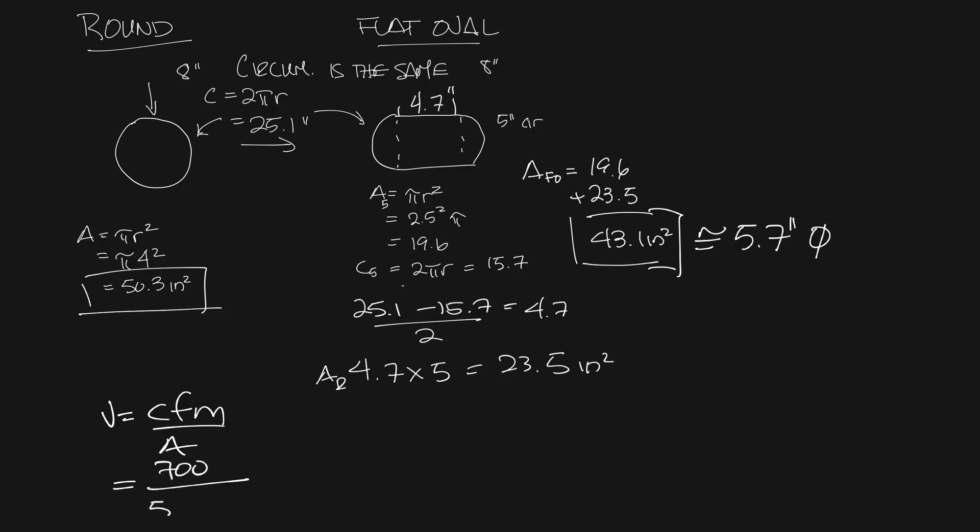That would be 700 divided by 50.3 and then we're going to multiply that by 144 to get us into feet. And that is about 2004 feet per minute for 700 CFM through an 8 inch round.